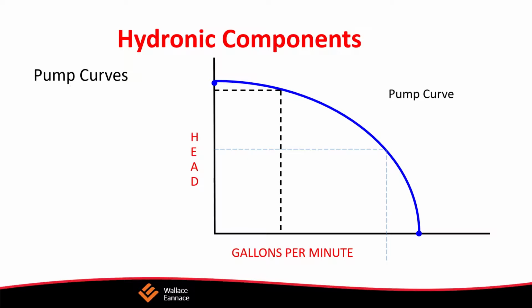which poses the question, which building will get a bigger pump? Well, if you look at these two buildings, really, it doesn't matter. If we push the water up this building and it comes back here, the only thing it has to do is overcome the piping in the building. The same is here. The pumps that are required for these two buildings are identical. So how do we calculate the required pump head?